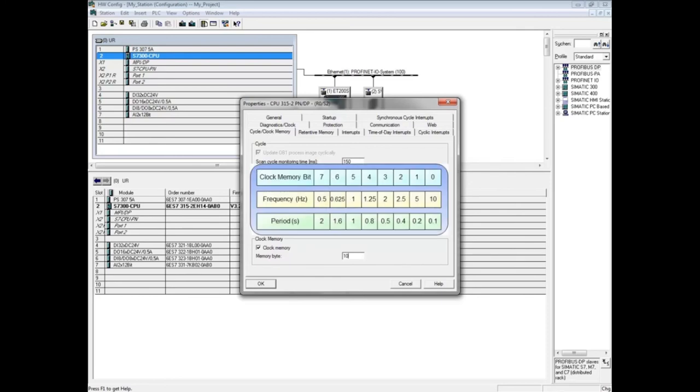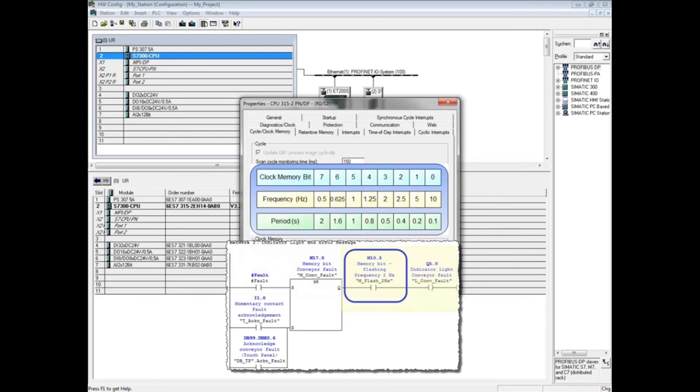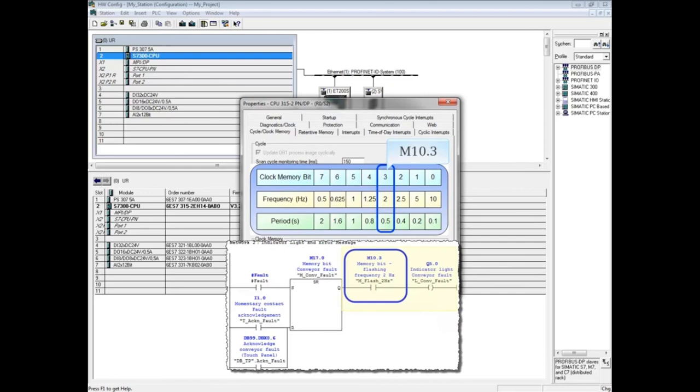In the code example, memory bit 10.3 will cause output Q5.0 to flash at a frequency of 2 Hertz. Or put another way, the bit will be true for 0.25 seconds and false for 0.25 seconds, for a total period of 0.5 seconds.